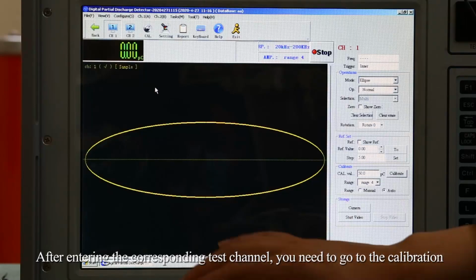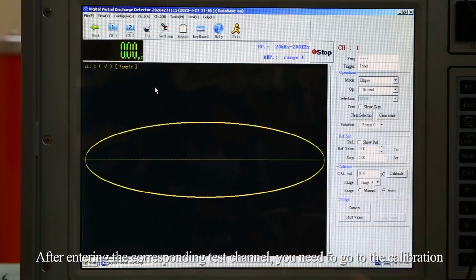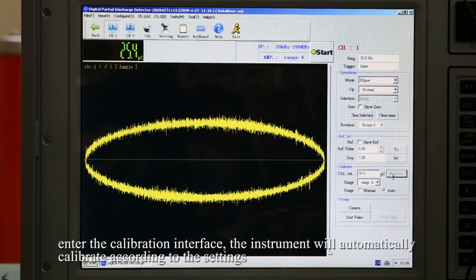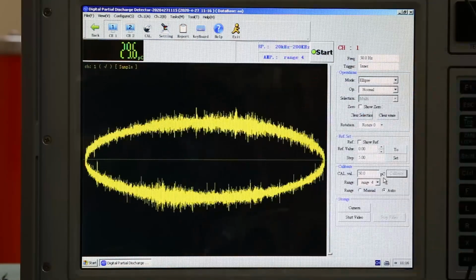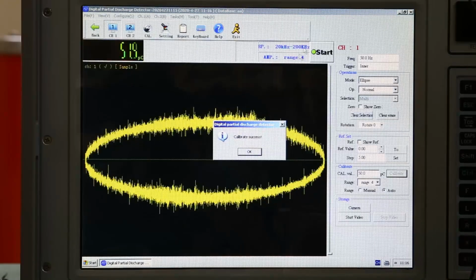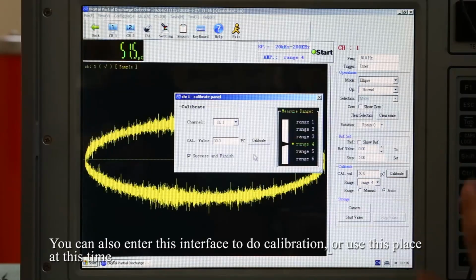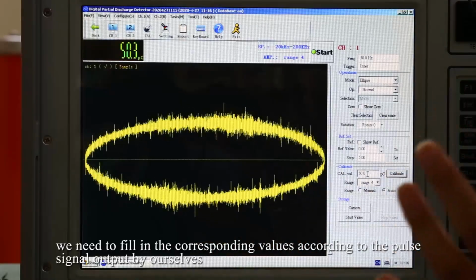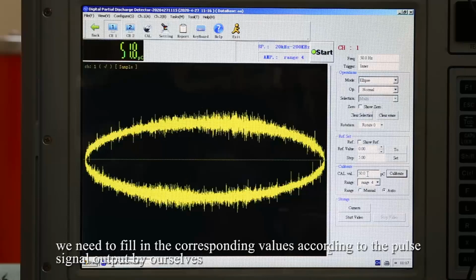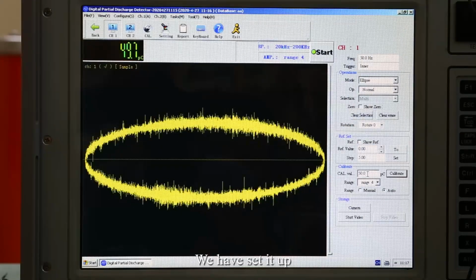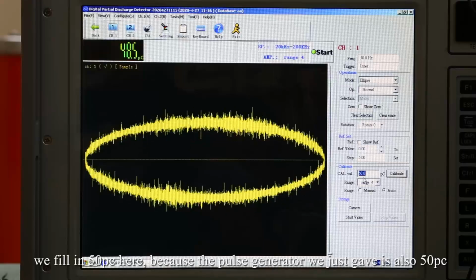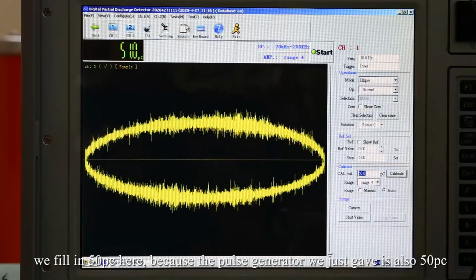After entering the corresponding test channel, you need to go to the calibration. Under the calibration interface, the instrument will automatically calibrate according to the settings. You can also enter this interface to do calibration or use its place. At this time, we need to fill in the corresponding values according to the pulse signal output by ourselves. We have set it up. We fill in 50pC here because the pulse generator we just gave is also 50pC.